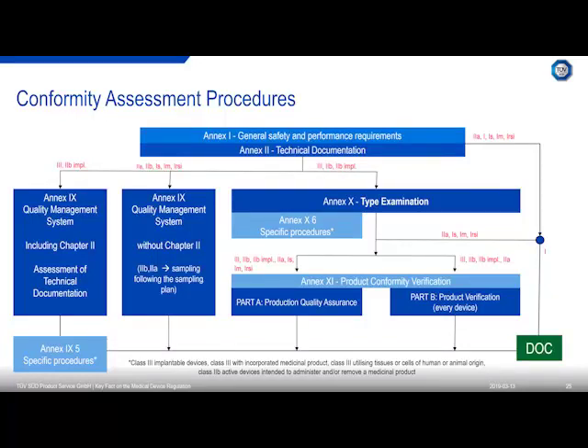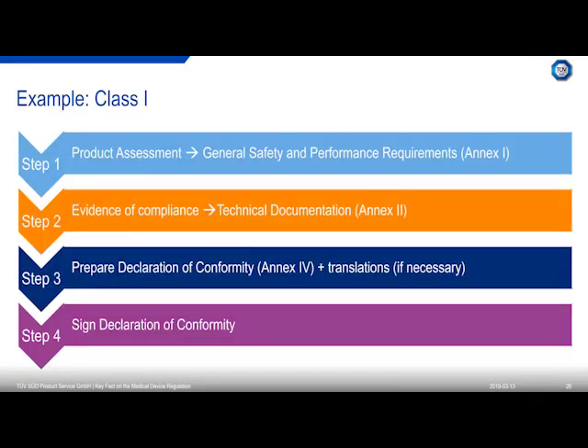So I picked out this one example because it's very important for a lot of manufacturers. Because class 1 devices will not have a transition period, because they don't have a certificate under MDD, because under AIMDD there is no class 1. So you don't have a certificate for a class 1 device under MDD. So for class 1 devices, there is no transition time. So you need to be compliant as of the first day of application of the MDR, which is May 2020.